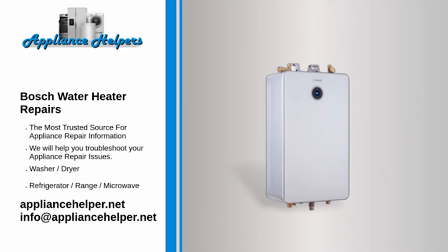No hot water. Step 1. Inspect the water supply. Connect the supply line to the blue inlet on the water heater. Step 2. Disconnect the power. Remove the cover on the water heater and reset the high temperature thermal cutout. Push the reset button in the center of the cutout. Reconnect the power.